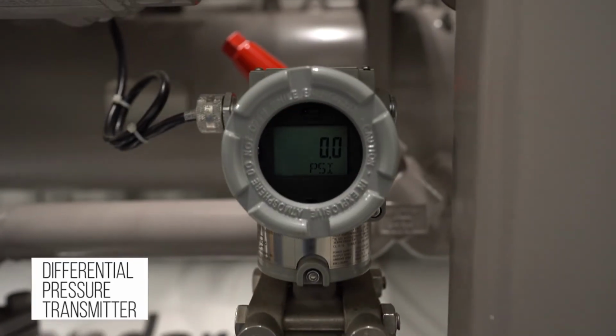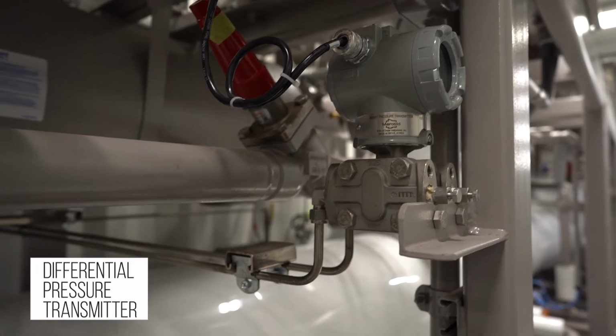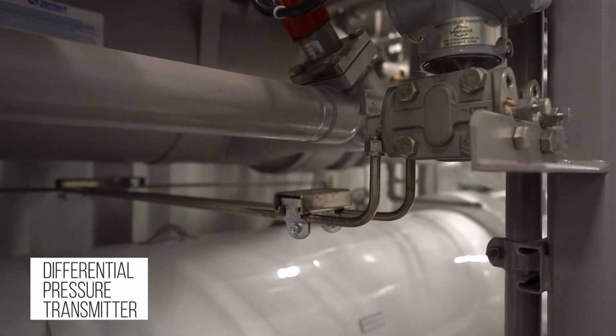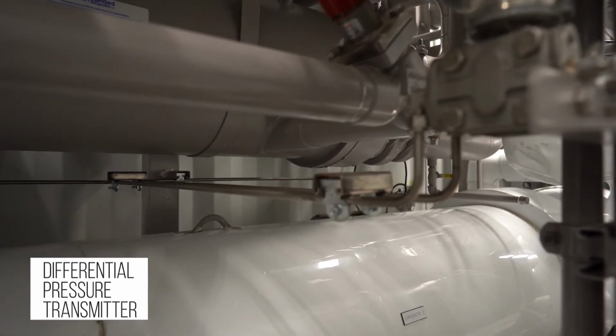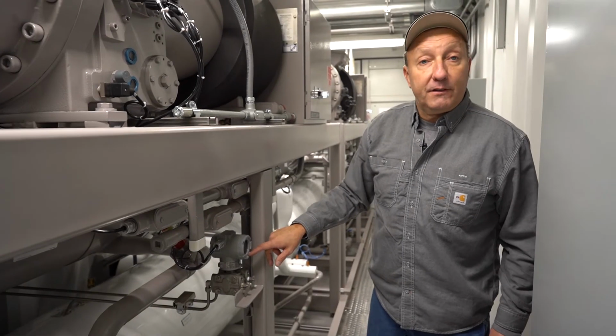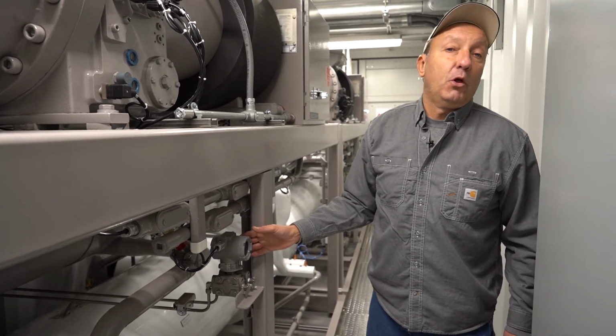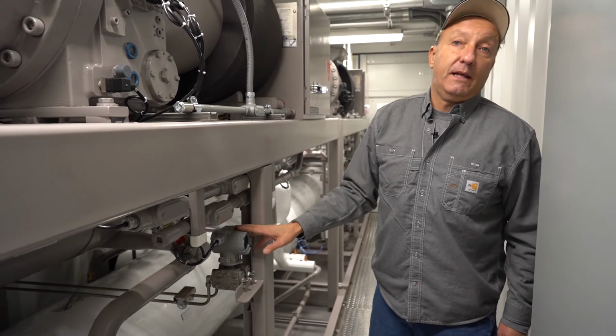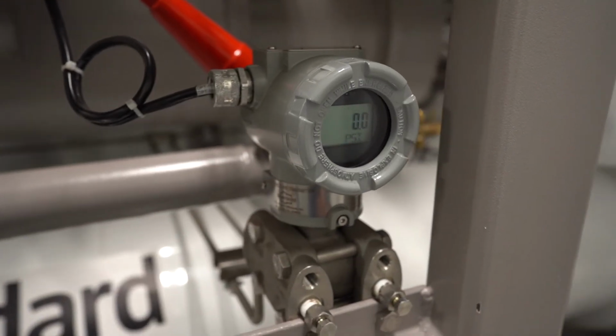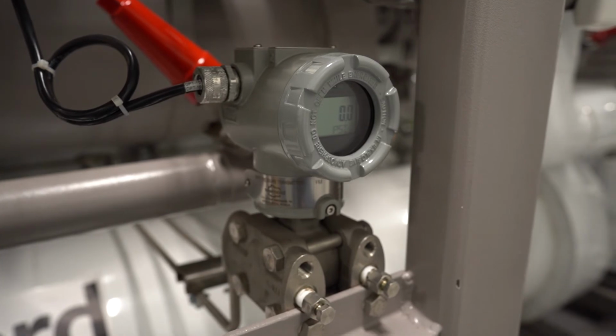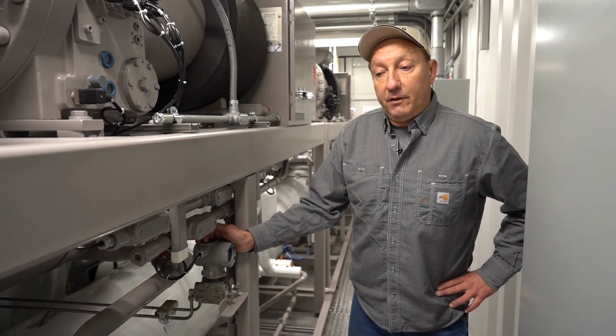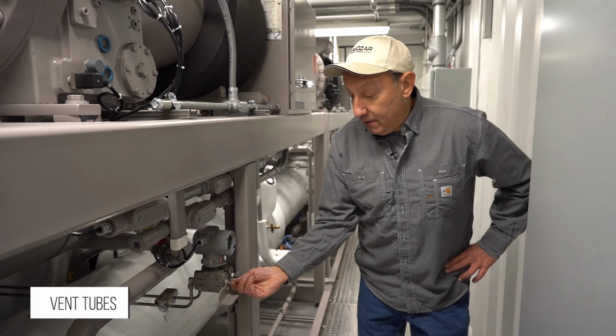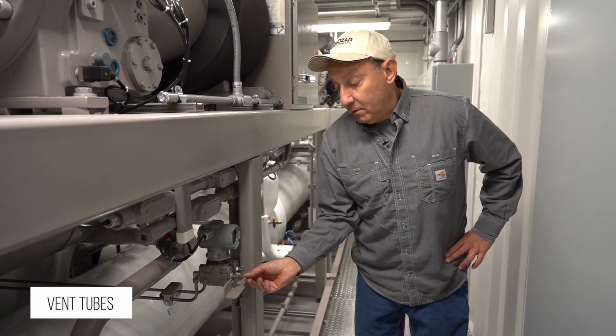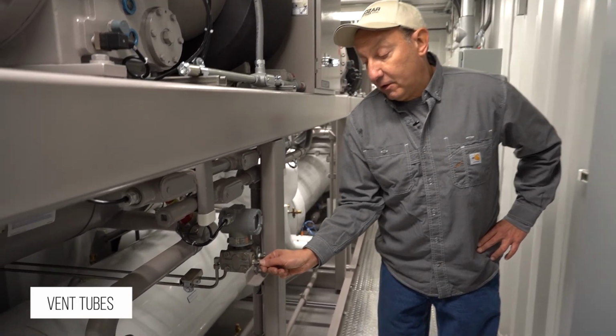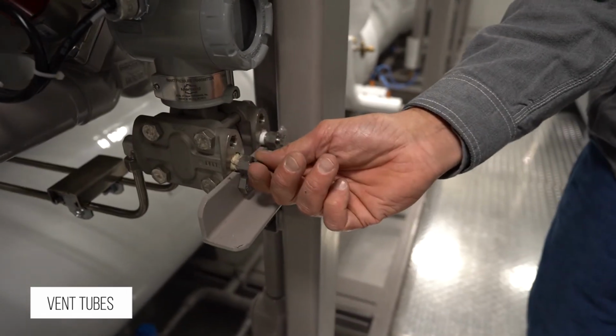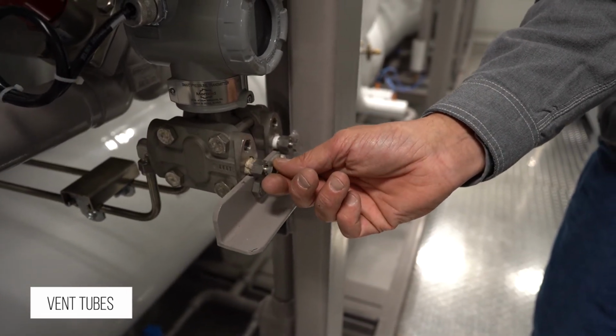Okay, this is our differential pressure transmitter. Basically, we have a tube going to the evaporator inlet and outlet, and we display the PSID, pressure difference across the evaporator. This is basically our flow acknowledgement. This is also displayed at the HMI and the main control panel. Anytime the system is drained or refilled or isolated for service or maintenance, we have the vent tubes here. Each tube, you get a small wrench and turn this counterclockwise, and there's a weep hole to vent the air out of the pressure differential transmitter.